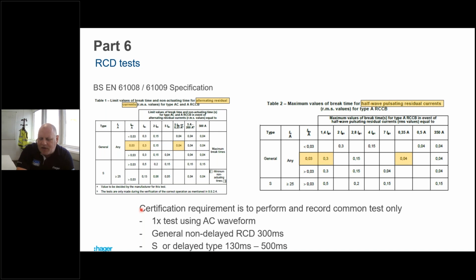One of the things they did realize though is that while we're using these devices, they are always sitting on an AC waveform, and that's where they mainly get used. They may be immune to DC faults blinding them, but they still sit on an AC waveform, and that is where we want them to operate. So they've decided for certification requirements now, we only have to perform one test. It's a 1 times test, using the AC waveform, at its rated current, basically.